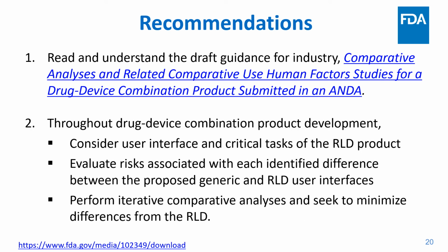So our recommendations to the industry would be to make sure you read and understand the draft guidance, the comparative analyses, and related comparative use human factors studies for a drug-device combination product submitted in ANDA. Throughout the drug-device combination product development, consider your user interface and the critical tasks required to be performed in the RLD product. Evaluate each of the risks associated with the differences between the proposed generic and the RLD user interface. You want to perform iterative comparative analyses to seek to minimize the differences from the RLD.